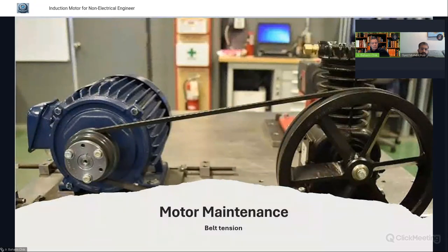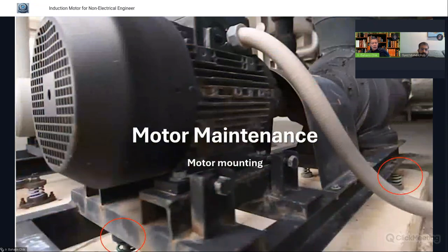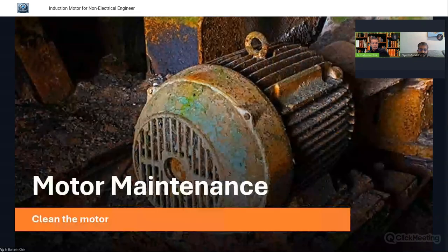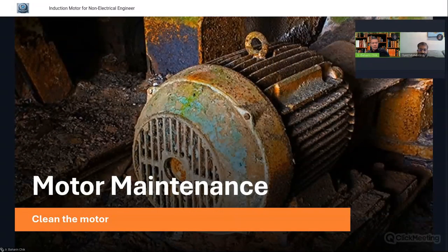For the belt mounting motors, belt driven motors, we also need to check the belt tension as a part of motor maintenance. Over here, we have seen that the pumps and motors are mounted together in one common mounting. So this needs to be checked also to avoid any vibration by the driving machine. Also, you need to clean the motors. Don't leave it like this; it's so dirty.